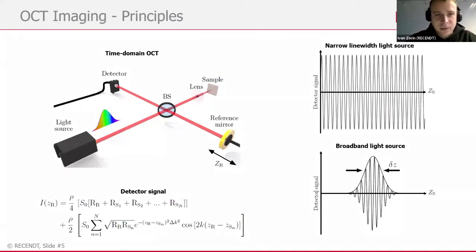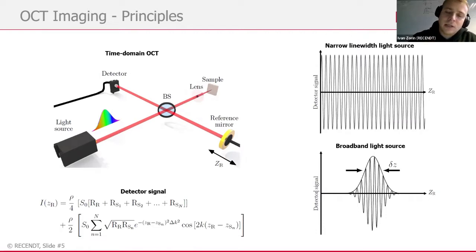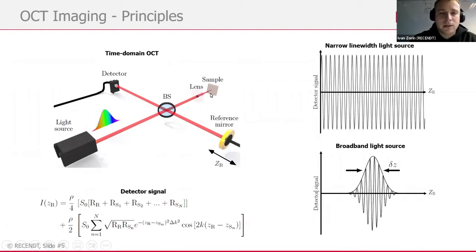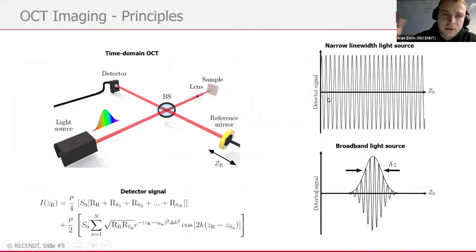This is a basic time domain OCT system. It's very good to start with time domain because it was the original historical implementation of OCT. It's based on a Michelson interferometer and exploits low coherence interferometry to get subsurface morphological information about the sample. We will see interference only in the case where the arms of the interferometer are nearly the same length — within the coherence length of the light source. If you take a quasi-monochromatic light source, we will see interference along some meters or even 100 meters. But if we take a broadband light source, the interference will be observed only within the coherence length, and this is what is exploited in OCT.